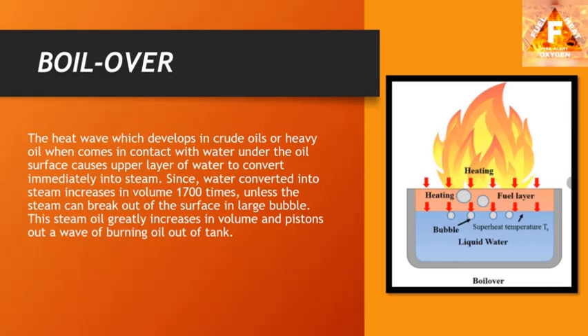A boil over can occur in prolonged tank fires containing petroleum mixtures with a wide range of boiling points, such as petroleum crude oil and certain fuel oils. Now let me explain the concept of boil over with the help of this diagram.